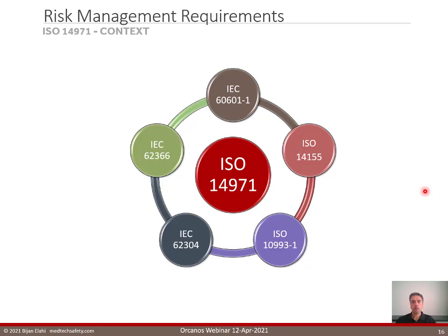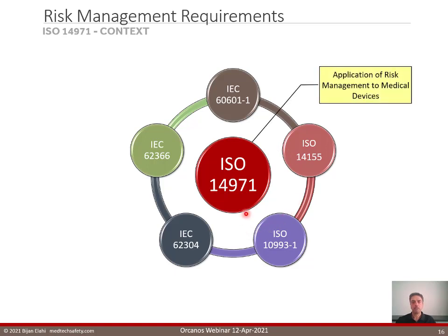I want to give you a little context about ISO 14971. ISO 14971 is the central standard for safety risk management of medical devices. There are a number of other safety standards that are applicable to medical devices, and they make normative references to ISO 14971. Here I'll give you 5 examples. So first, the standard definition of the ISO 14971 is the application of risk management to medical devices.